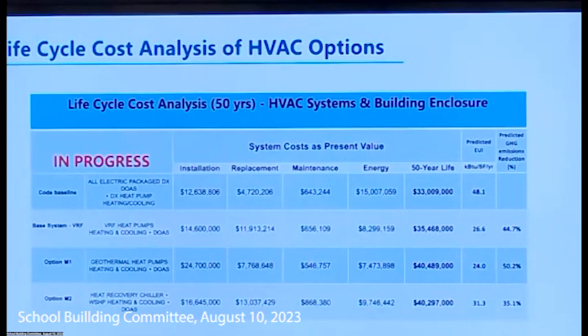But for the 3 systems we studied, the base system is the air-cooled VRF system. If you've seen those wall-mounted air conditioners in homes, a doctor's office, or elsewhere, that's that kind of system. It has an outdoor condensing unit with refrigerant piping connected to an indoor fan coil unit. A typical classroom would have a fan coil unit with ductwork serving that classroom, connected through refrigerant piping to an outdoor unit. That system, on a 50-year life cycle basis, is the most cost competitive.